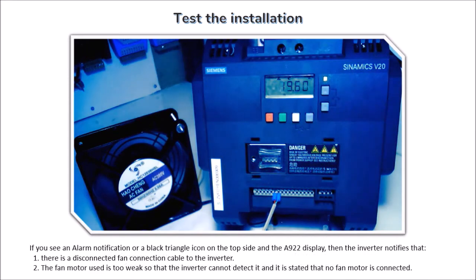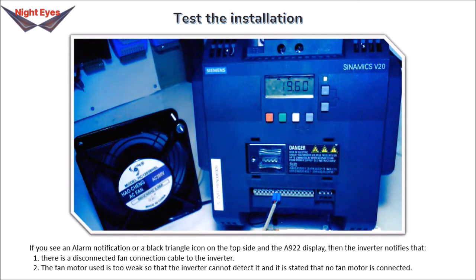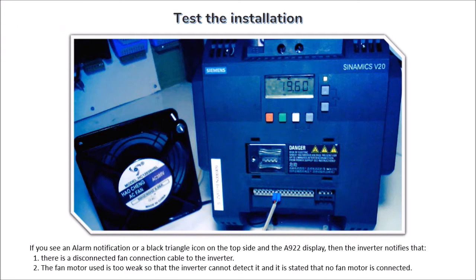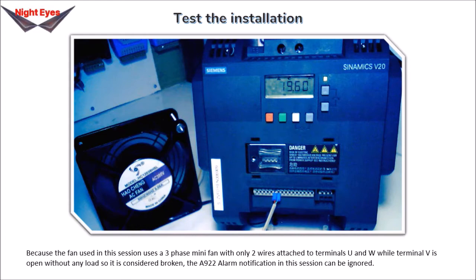If you see an alarm notification — a black triangle icon at the top and the A922 display — the inverter is notifying that: 1. there is a disconnected fan cable, or 2. the fan motor is too weak for the inverter to detect. Because the fan in this session is a three-phase mini fan with only two wires attached to terminals U and W while terminal V is open, the A922 alarm notification can be ignored.